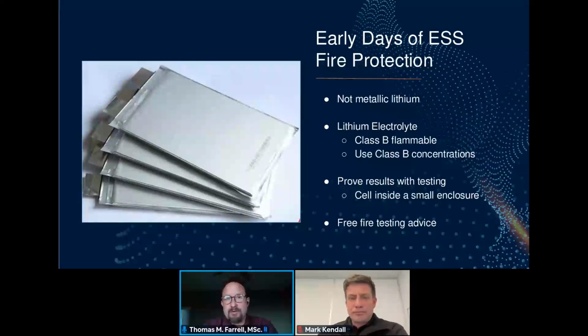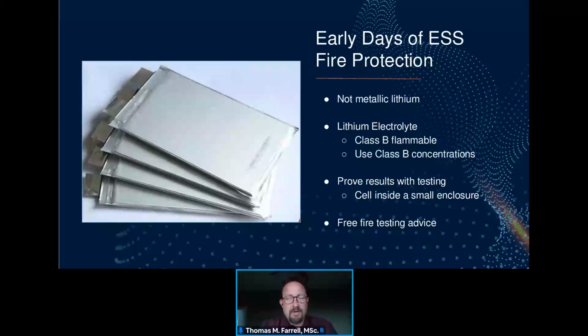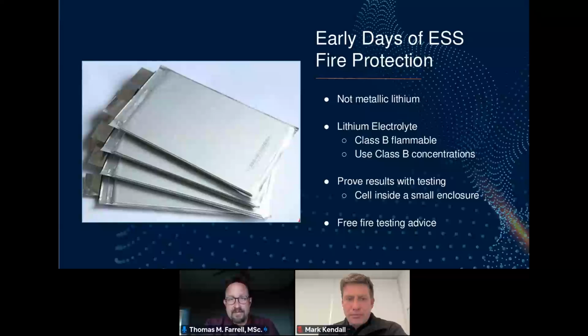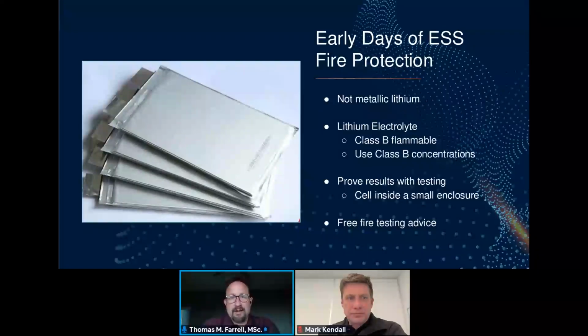The biggest problem with those demonstration tests is that when one cell goes into thermal runaway and creates a fire, in most videos you find on YouTube, the cells aren't electrically connected to each other. Also, the events are relatively short-lived in terms of energy release from stored electrical energy. So what's left after that initial release looks like a traditional fire—it's the plastics remaining, the mylar catching fire—and inert gases or clean agents can put that fire out pretty well.